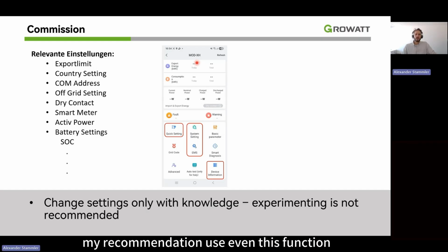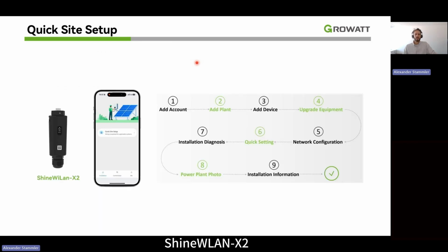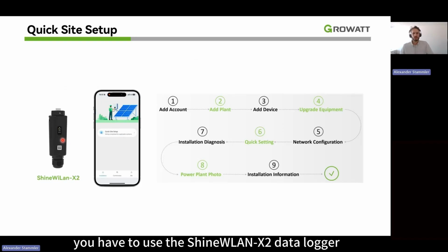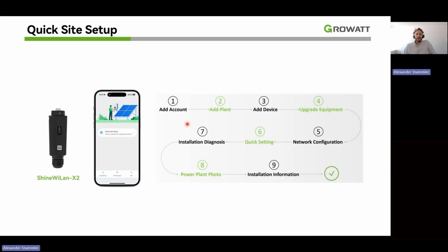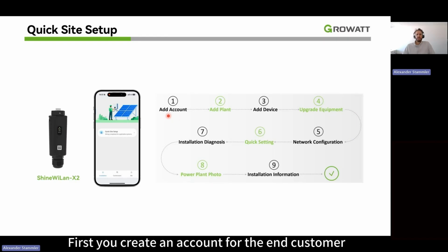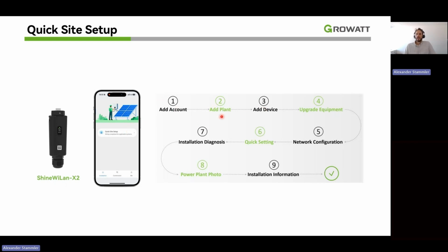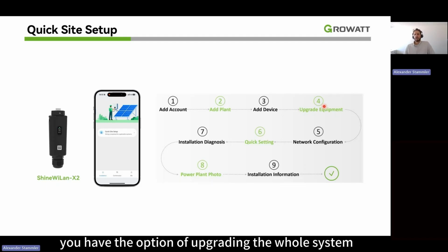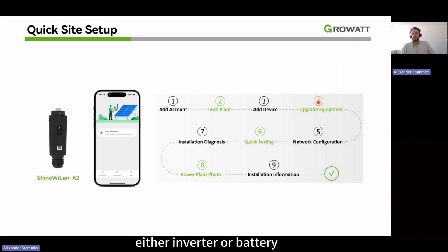My recommendation: use even this function only with the ShineWiLan-X2. If you use the quick site setup, you have to use the ShineWiLan-X2 system data logger. What it does is it does the whole installation with you. First, you create an account for the end customer. Then you create a plant for the end customer. Then you add the device, the inverter, to your customer plant. You have the option of upgrading the whole system, either inverter or battery.